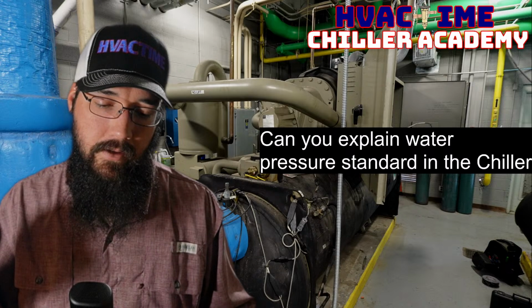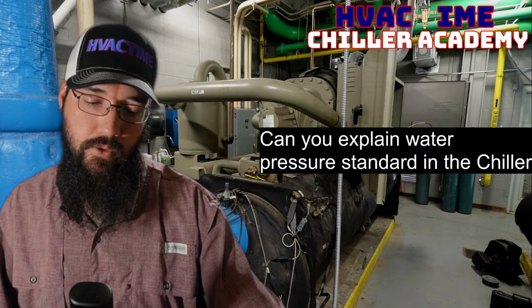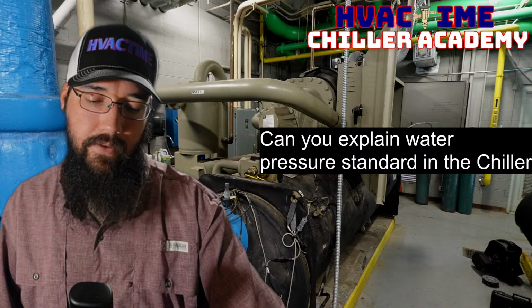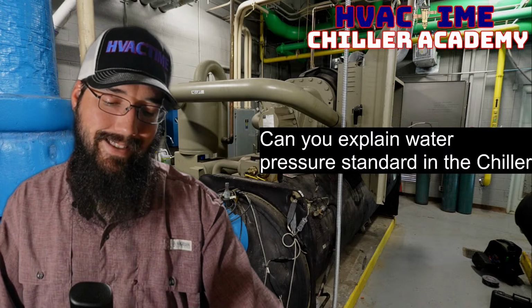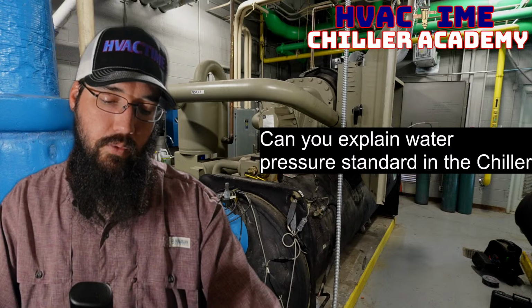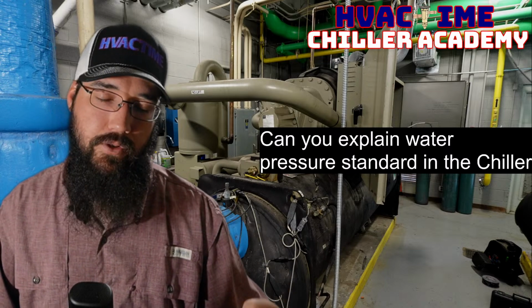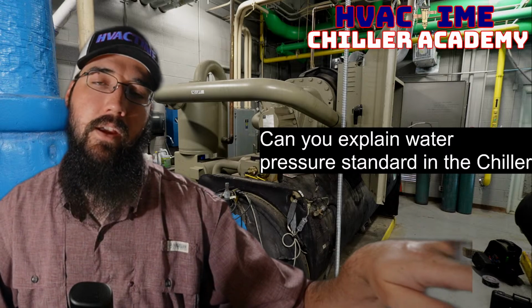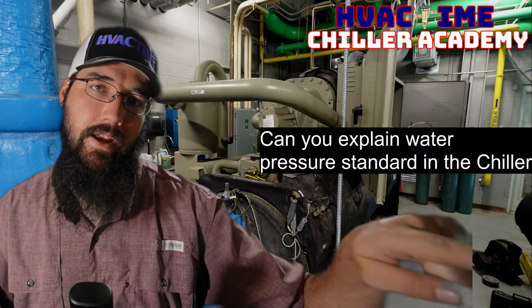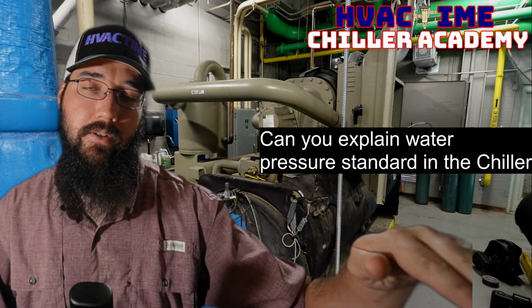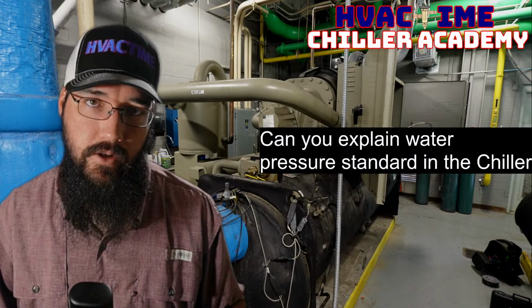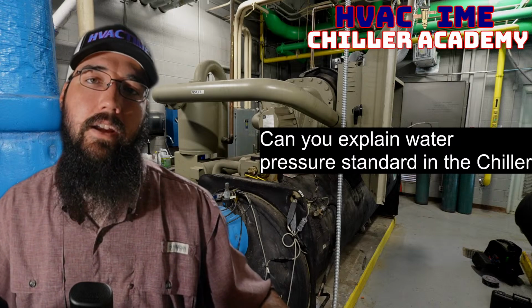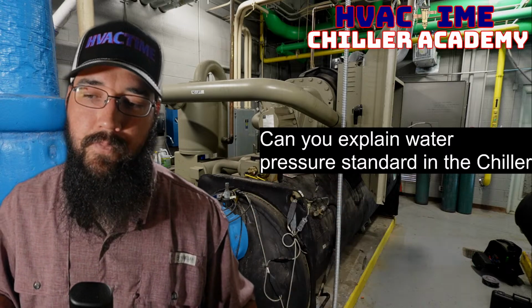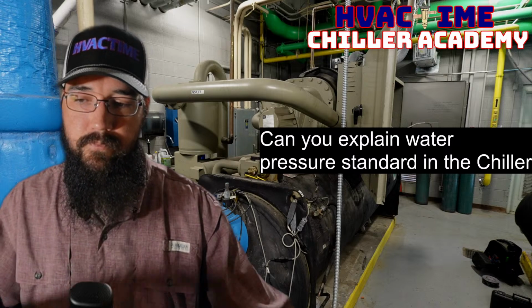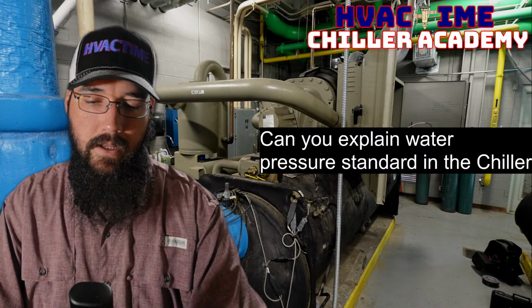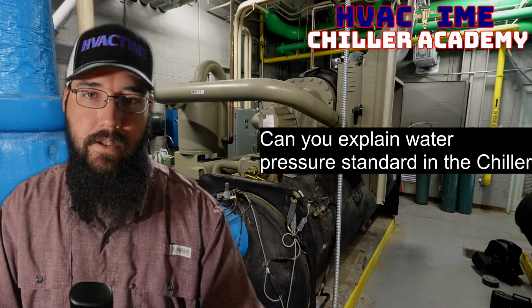2.31 feet per PSI. So if you had 14 or 15 feet of head, you would divide that by 2.31, and then that would give you what your DP is. So they want to see, say, 15 feet of head differential between your entering water and leaving water. You can convert that to PSID, and then that'll be what you set to. Now that's if you're trying to determine DP, okay, in this particular question.